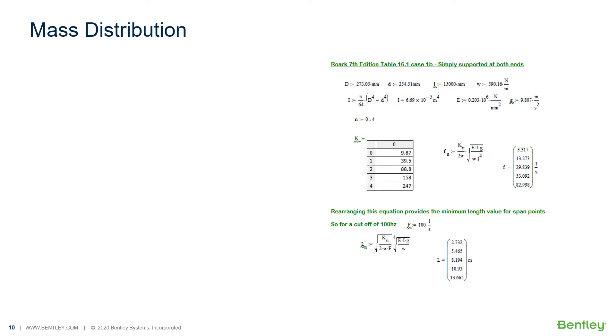It isn't practical to keep adding nodes to long lines until we achieve the correct results in a complex piping system, so we need an automated way to discretize our geometry. AutoPIPE uses the same equation from Roark, but this time it uses the equation for a simply supported beam, because that's what most of our piping models will be.